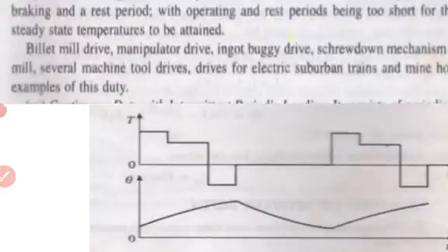Intermittent periodic duty with starting and braking: both are considered. Earlier only starting was considered, now braking is also considered. So during starting and braking there will be a temperature rise, and that is considered in this intermittent periodic duty with starting and braking. Okay.